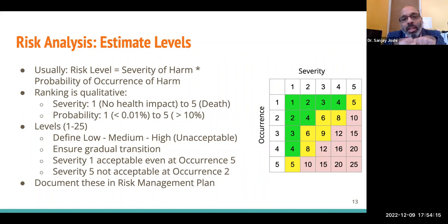But the first thing I would recommend is to go through the guidances. Different governments will have different guidances, and usually they are published on the government website, on whether you should even consider the product you are making as a medical device. If the government is going to treat your product as a medical device, then absolutely you need to follow all this. If not, it's really up to you. I would still say that it's a sane, safe thing to do, so that if anybody challenges you on what could go wrong, you at least have some documentation that proves it.